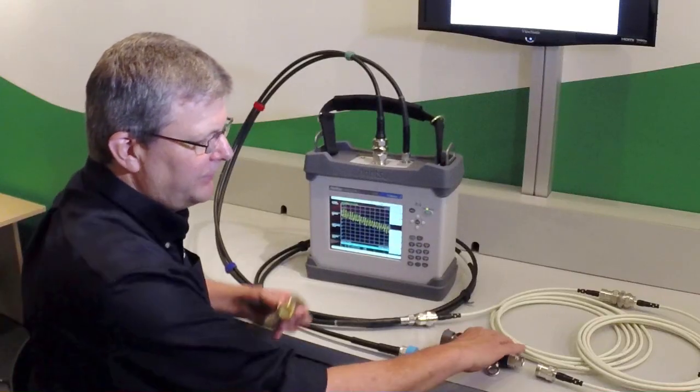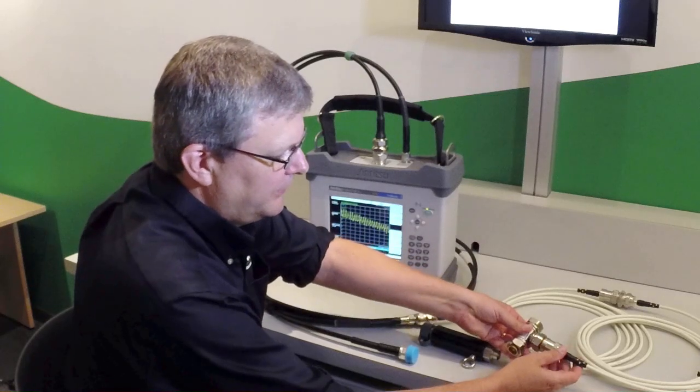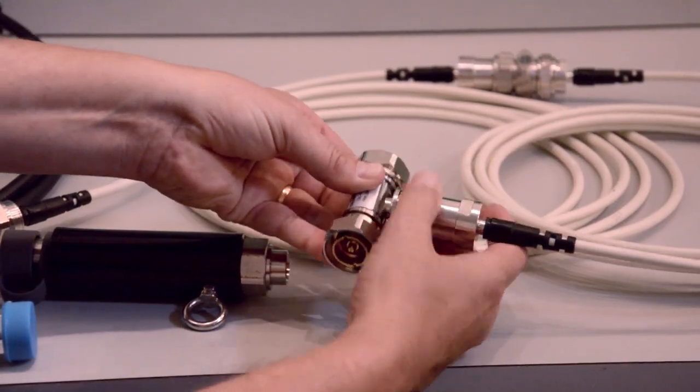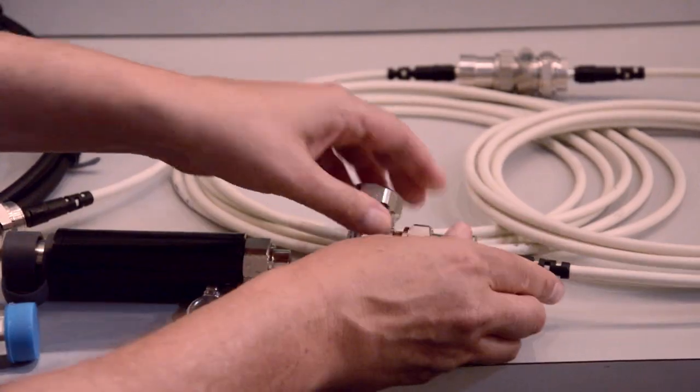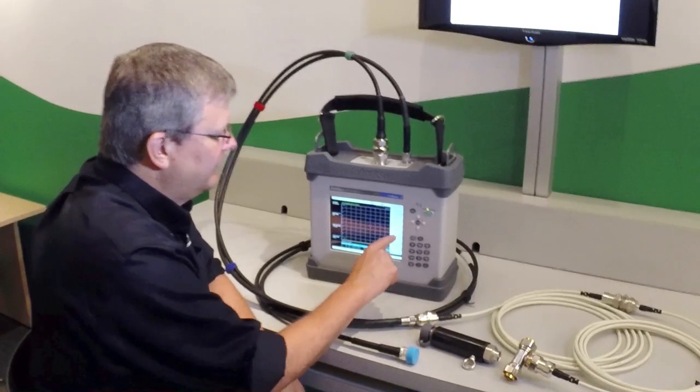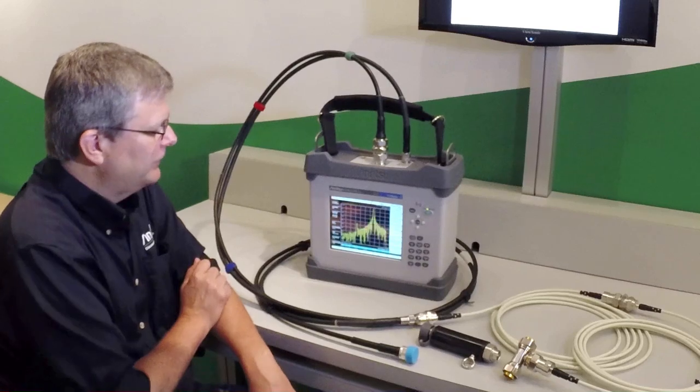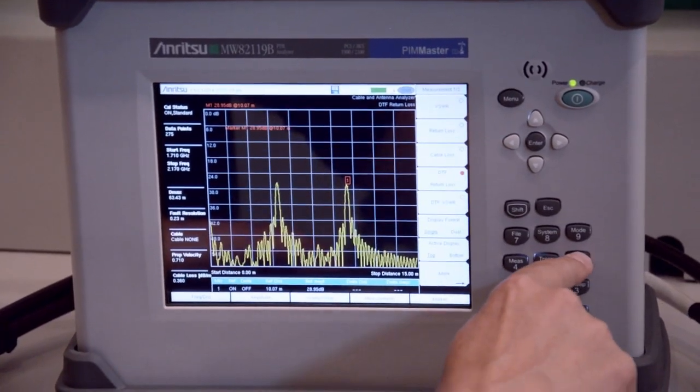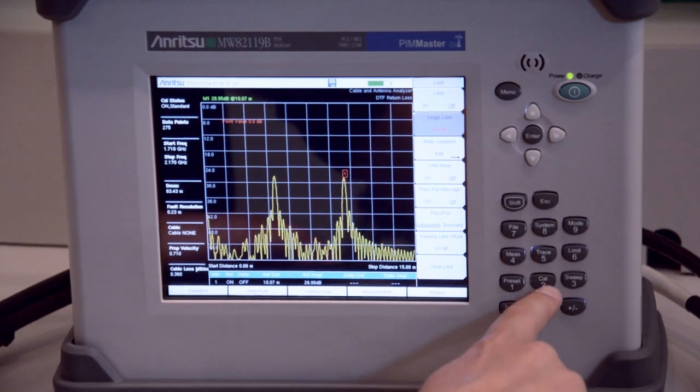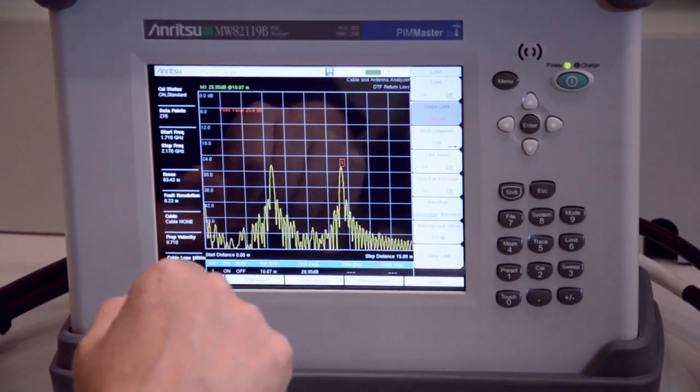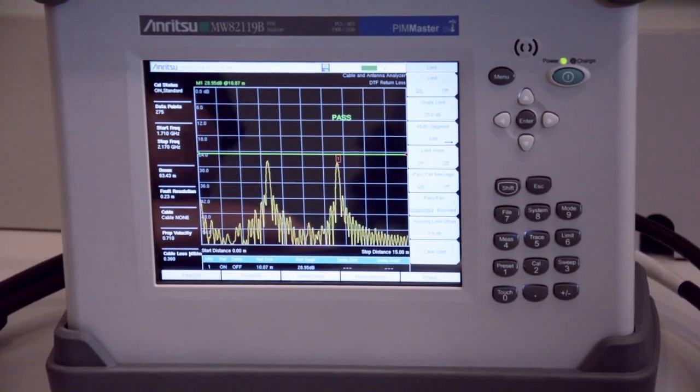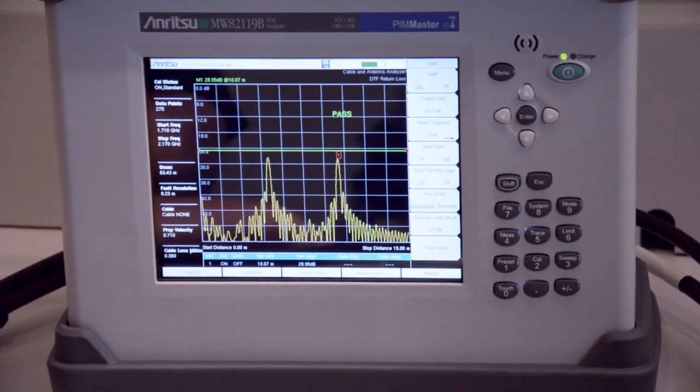The next measure we're going to do is attaching the precision load to the end of the cable and performing a distance to fault return loss measurement to look at the condition of the individual connectors. In this case, we'd like to see that the individual cables are below a 25 dB level to show that each individual cable is put together correctly.